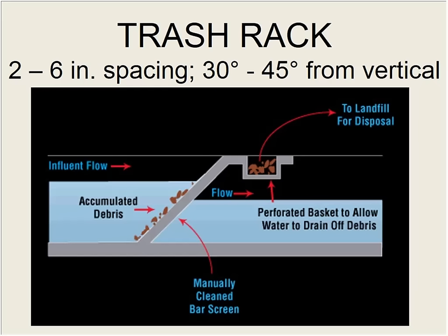This is a trash rack. These aren't so common. You may find these in lagoon systems or very small operations. But the principle is kind of the same. We've got a series of bars set at an angle to the wastewater coming in, and they're spaced. The trash rack is very crude, 2 to 6 inches. So some big stuff will still flow through here, but anything that doesn't fit between those bars gets caught on the bars.